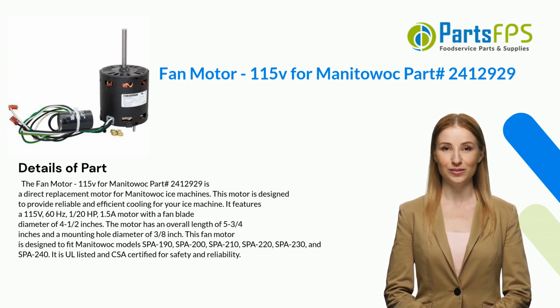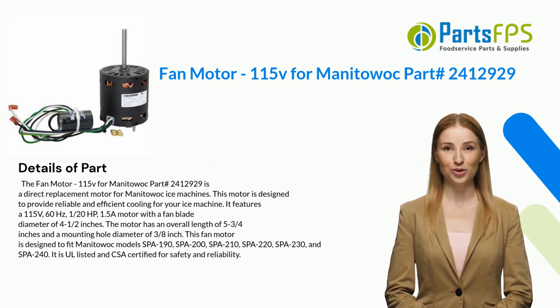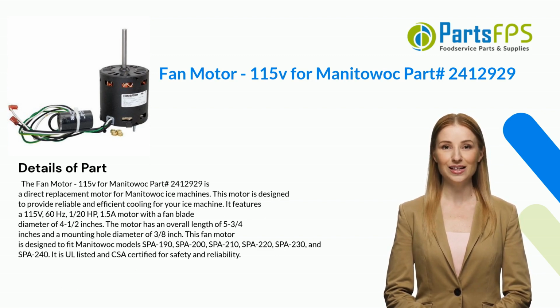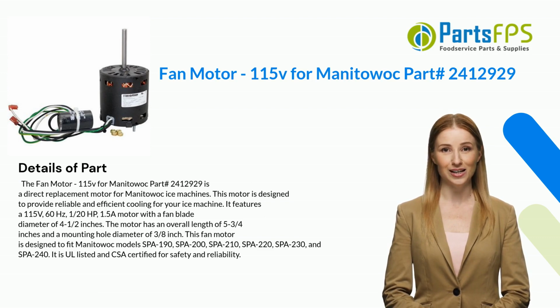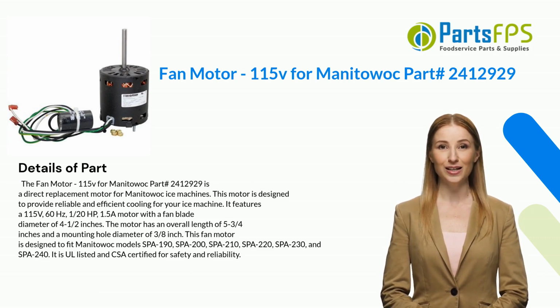It features a 115V, 60 Hz, 1/20th HP, 1.5A motor with a fan blade diameter of 4.5 inches. The motor has an overall length of 5 3/4 inches and a mounting hole diameter of 3/8 inch. This fan motor is designed to fit Manitowoc models SPA 190, SPA 200, SPA 210, SPA 220, SPA 230, and SPA 240. It is UL listed and CSA certified for safety and reliability.